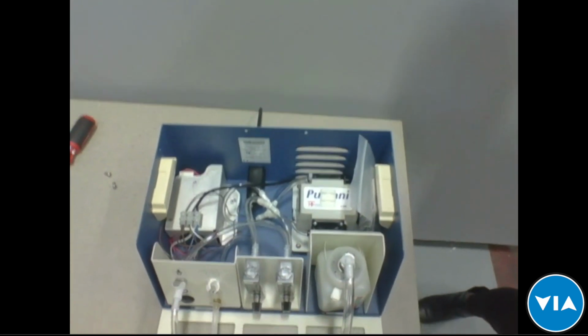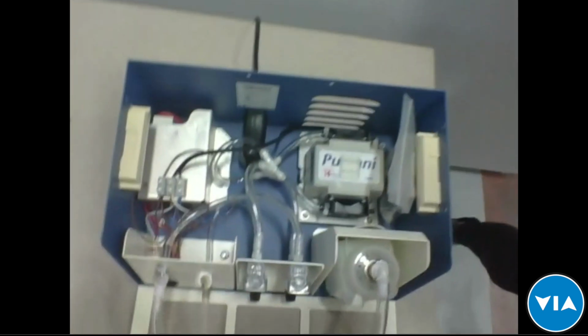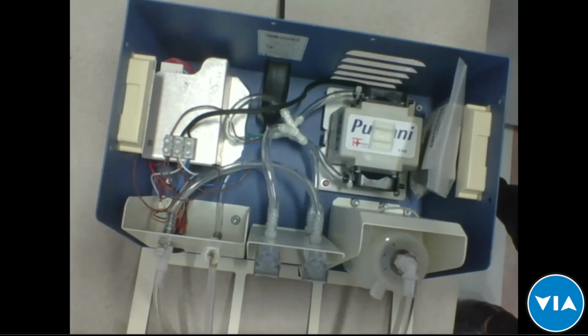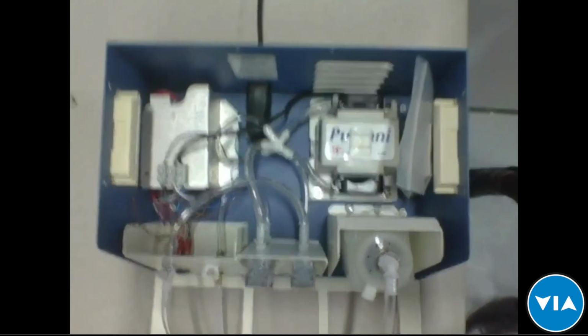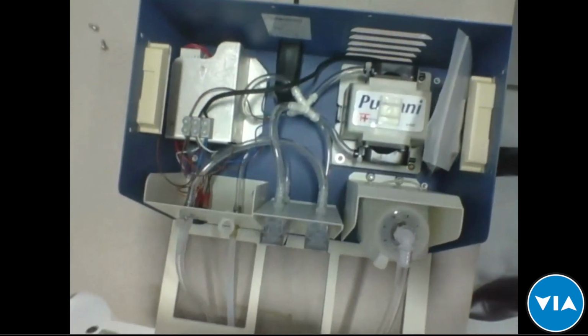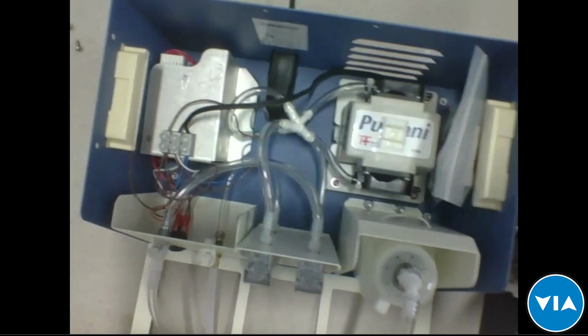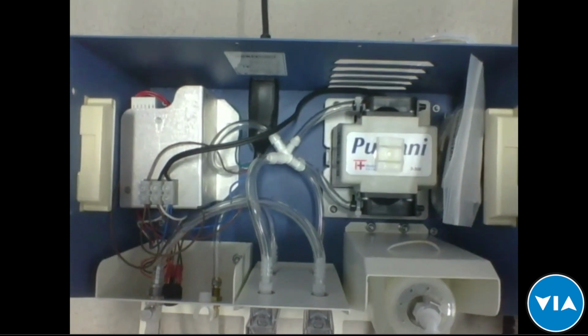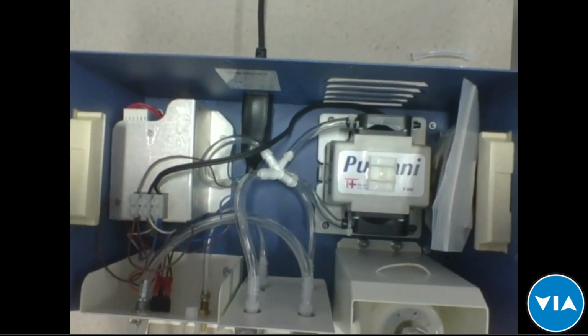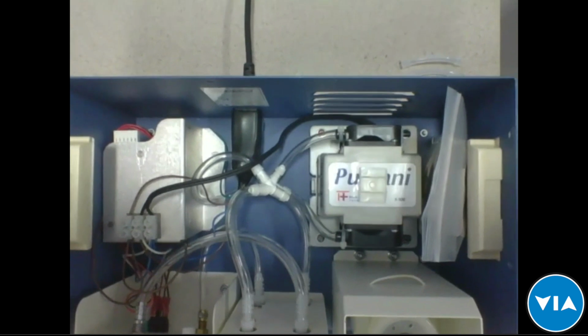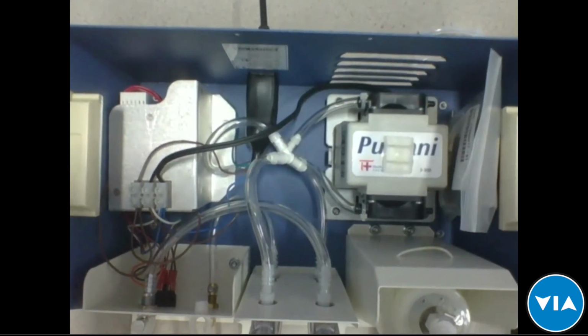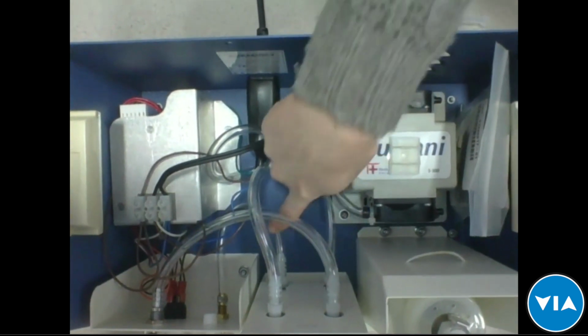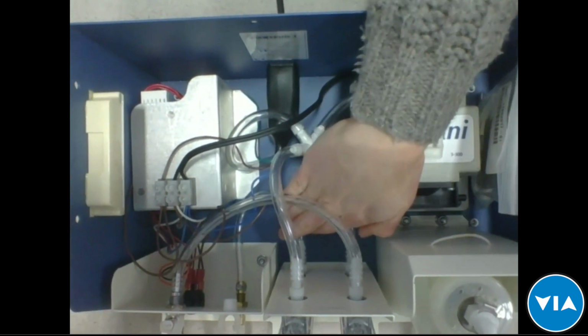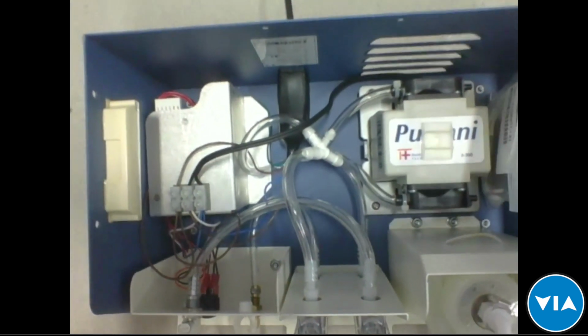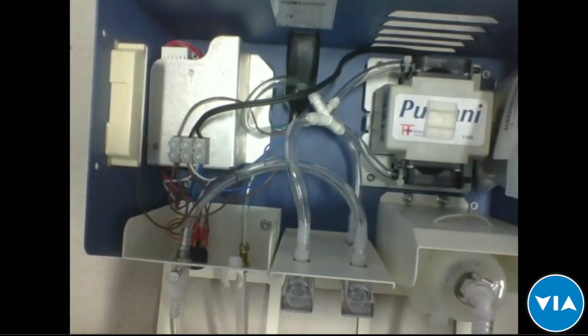Right. So if you look inside, and these tubes are all connected, you'll see that there are 4 tubes on the flow meters going to various places. All of those tubes should be connected. There shouldn't be anything loose that's just hanging in the air. Likely the problem you're seeing is that one of the tubes, likely the bottom one on the oxygen flow meter, is popped off. And all you need to do is push it back on, close the machine, and start running it again, and make sure that oxygen flow meter stays open.